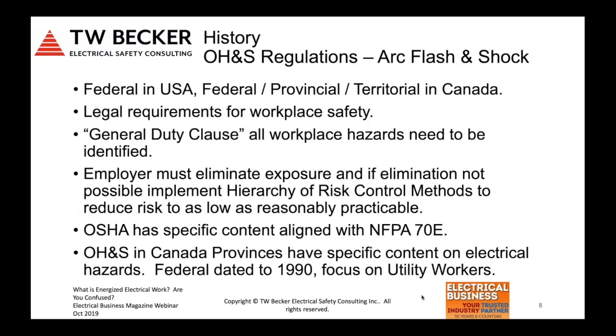As far as the OH&S regulations, there's been evolution here in recent years in Canada specifically. But just to summarize, the OH&S regulations both in the US for OSHA and provincially, territorially, or federally in Canada, there's the general duty clause, which really employers were supposed to identify all workplace hazards, eliminate exposure, and if they couldn't eliminate exposure, reduce risk by applying what's called the hierarchy of risk control methods. So again, OSHA has specific content, in this case on NFPA 70E, that's evolved over the years. In Canada, we have had in the last 10 years some electrical safety specific content added to the regulations.